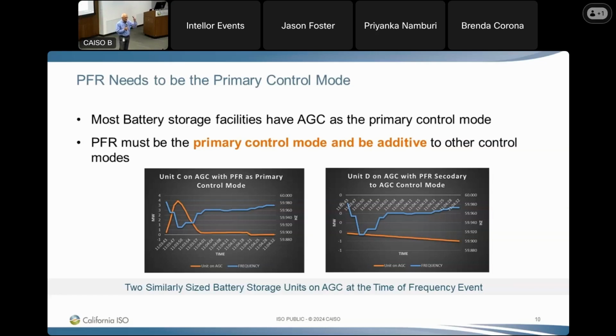But IBRs are so beautiful in their response, as you can see here. I have another presentation with an example of a battery storage unit that has a 4 second delay. I contacted that unit, not because there's anything wrong, but to ask why they had this 4 second delay given that the vast majority of units I look at respond right on time. They investigated, and it turned out to be the relationship between the controller and the inverter, and sometimes one of them isn't in sync.